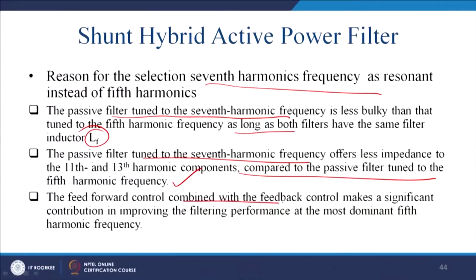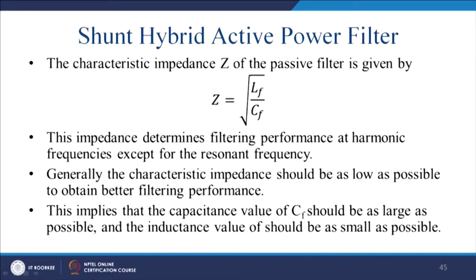The feed forward control combined with the feedback control makes a significant contribution in improving the filtering performance at the most dominating 5th harmonic frequency. The characteristic impedance Z of the passive filter is given by Z equal to under root of LF by CF. This is also called the surge impedance, and we will see this impedance determines the filtering performance, because this will offer at the 50 hertz. This impedance determines the filtering performance at harmonic frequencies except the resonating frequency. So, the resonating frequency may be your 7th harmonic. So, what impedance will it offer? That will be in this value.